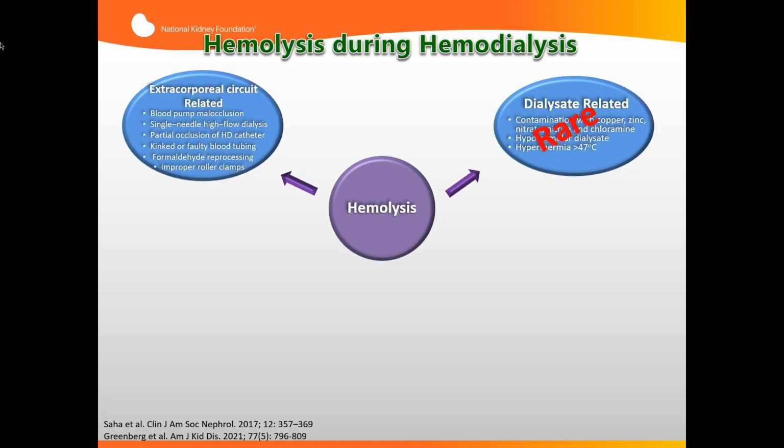Now, you have to understand the extracorporeal circuit is a laminar flow. So the red blood cells are exposed to differential shear stress between the center of that flow and the wall of the tubing. They can sustain differential shear pressure from minus 500 to plus 1500 and still not break. But sometimes the limits of that are really tested, and when they do break the red blood cell, that's when you typically get hemolysis.